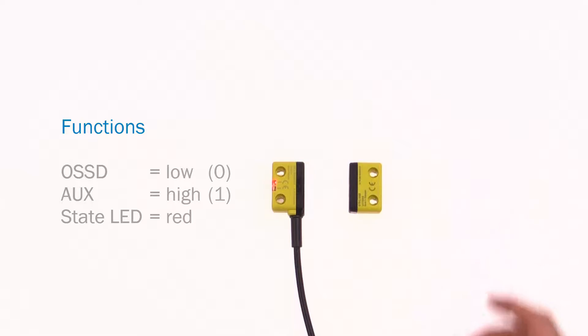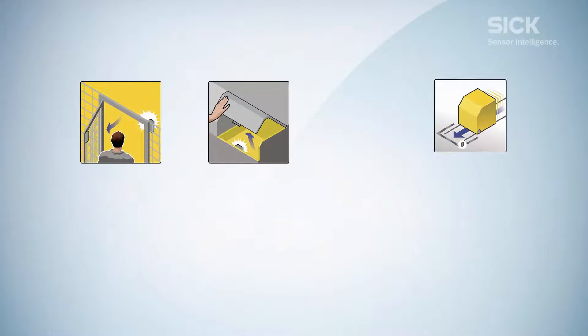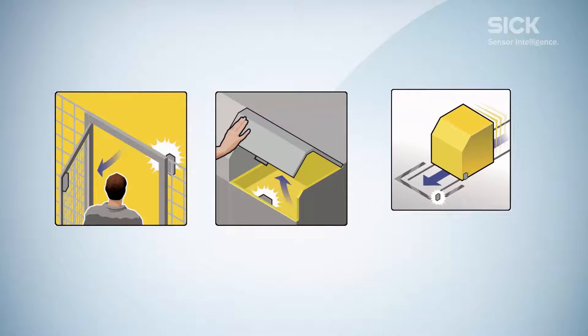The OSSD outputs switch to high only when a valid actuator is identified within the operating range of the sensor. This can be used to monitor the state of protective doors, opened or closed, or for safe position monitoring.